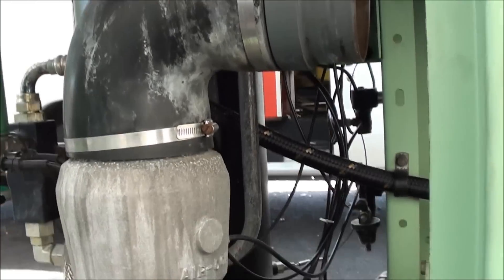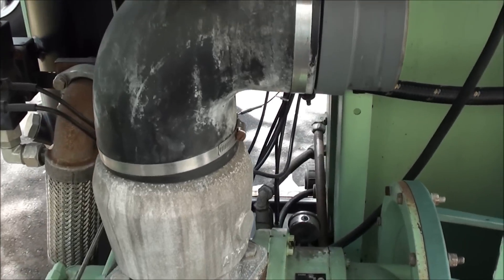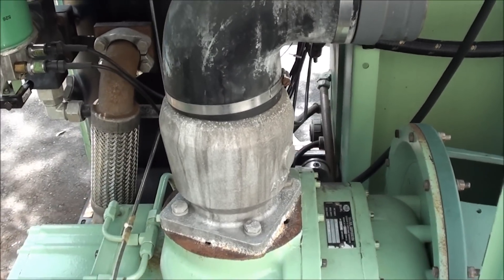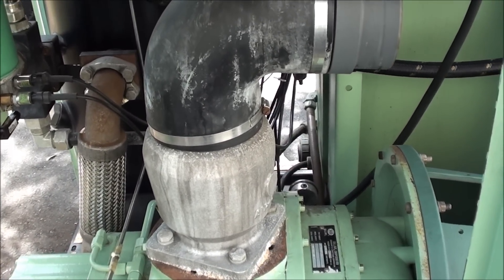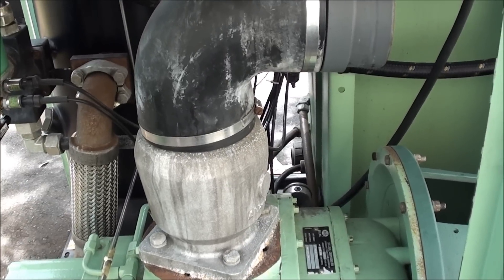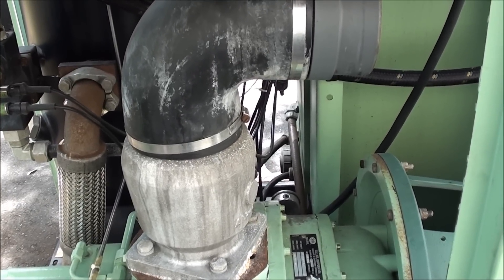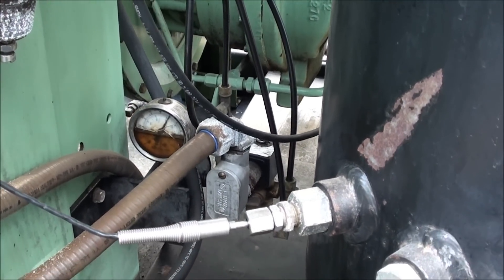There are two kinds of designs with rotary screw compressors: one is load-unload and the other is modulated. This machine is modulated and basically it'll match the demand for the plant air pressure, providing you don't use more air than the capacity of the compressor.